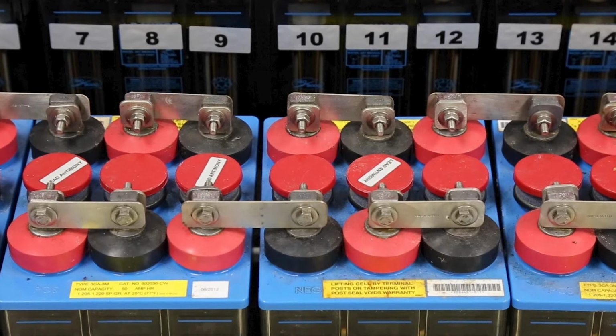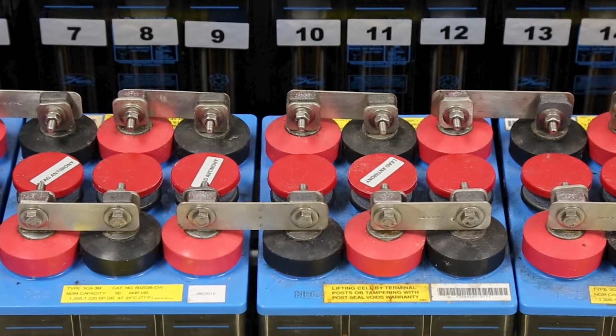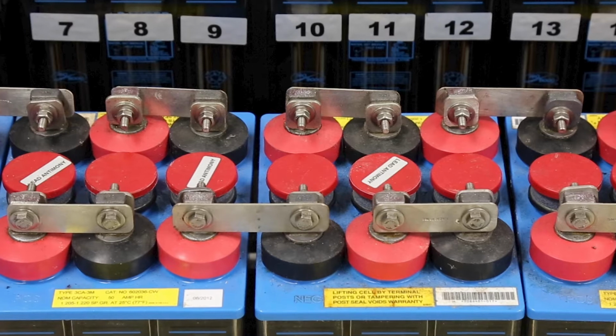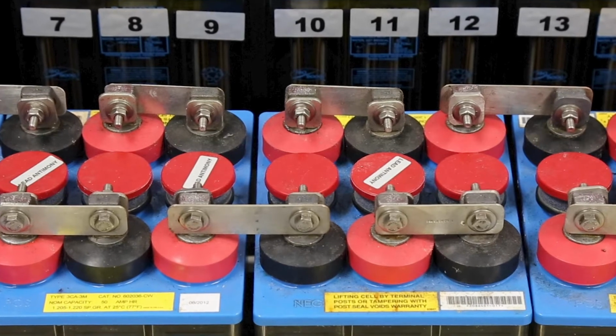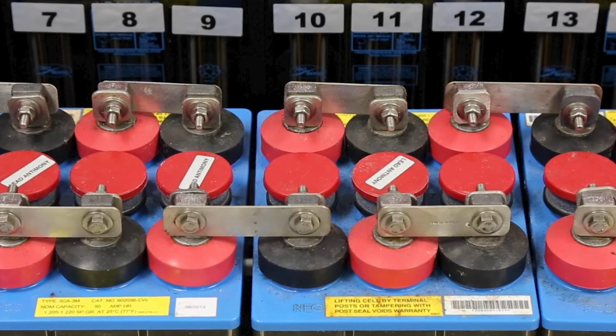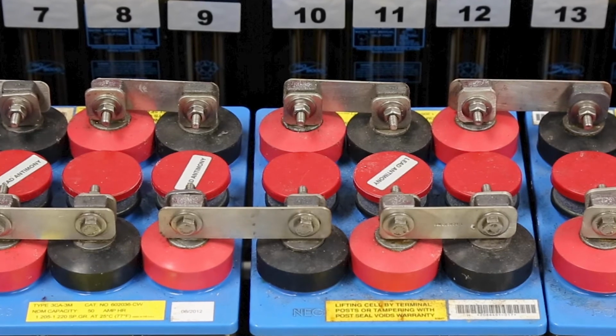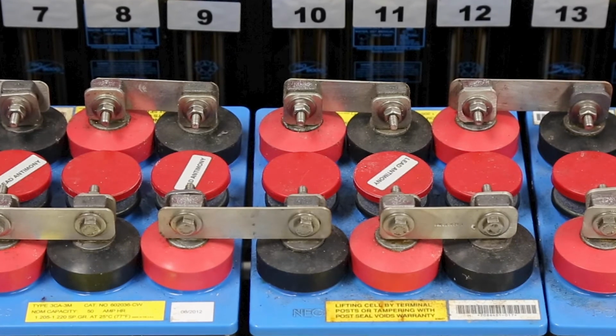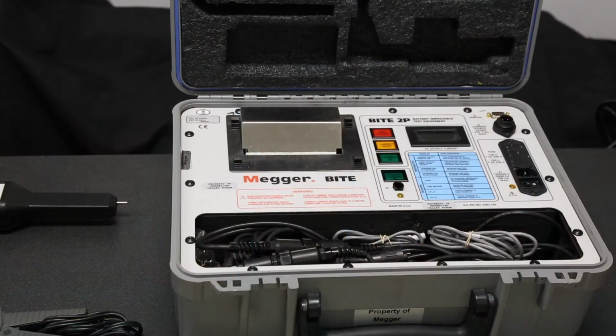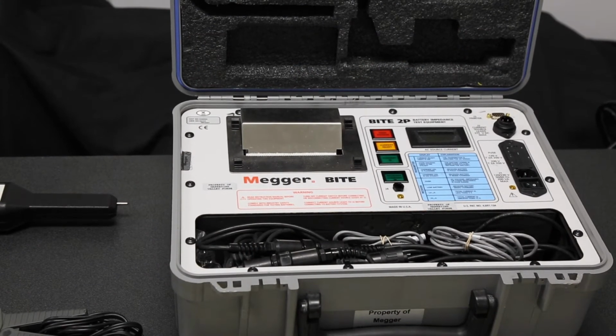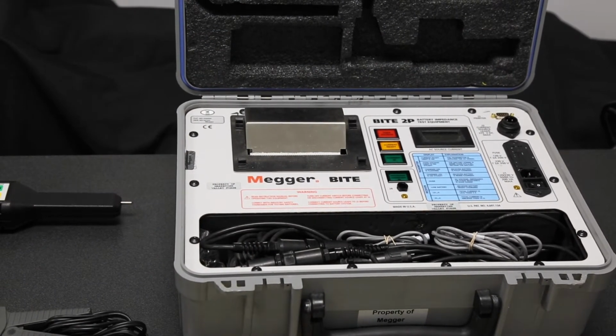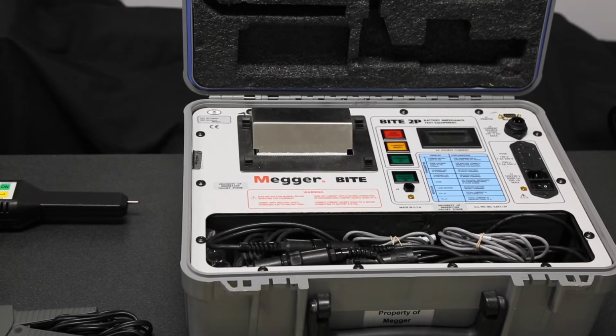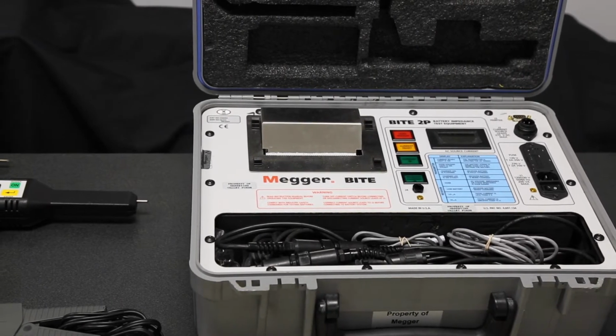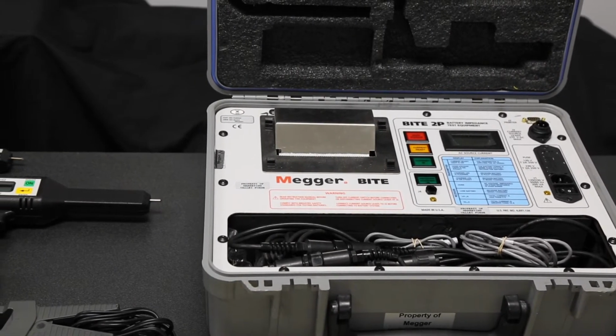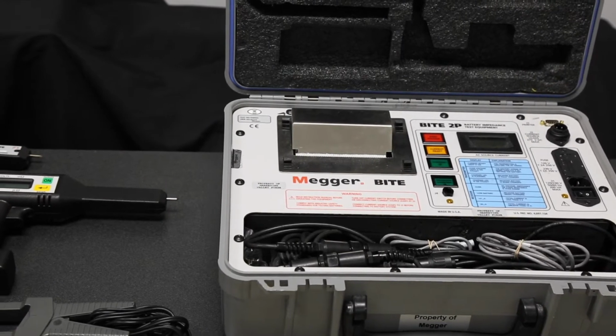A battery can be a source or a load. If this battery has a higher voltage than the one next to it, where does the current flow? Your string is only as good as the worst battery in that string. The BITE2 tests with 10 amps of test current. This allows you to test both large flooded batteries and the intercell connections with one single pass through the string.